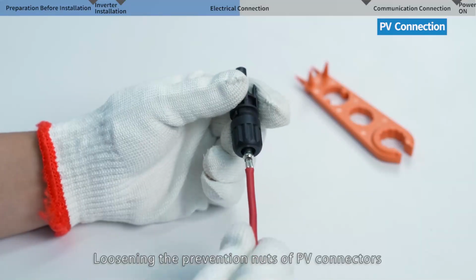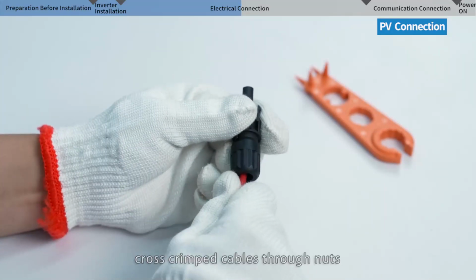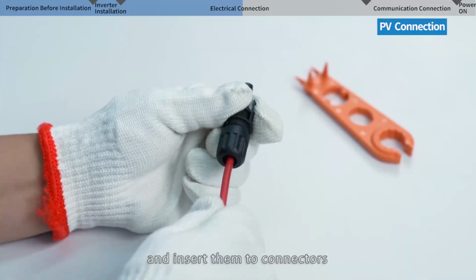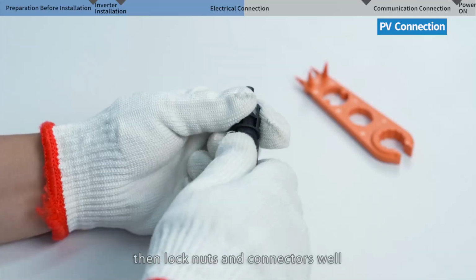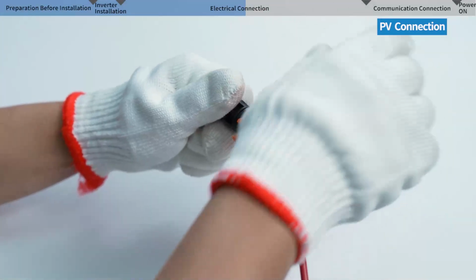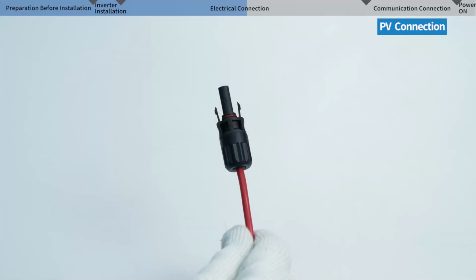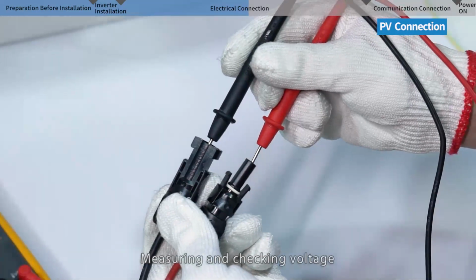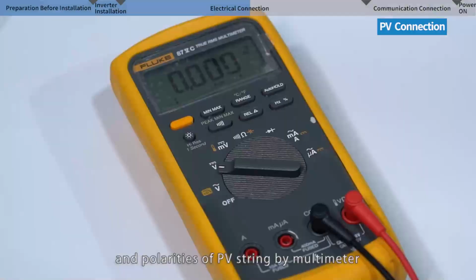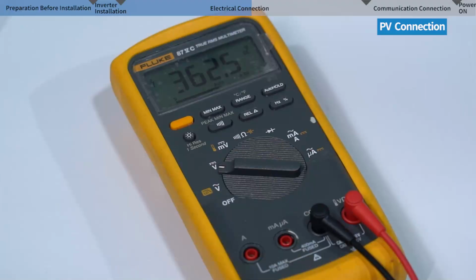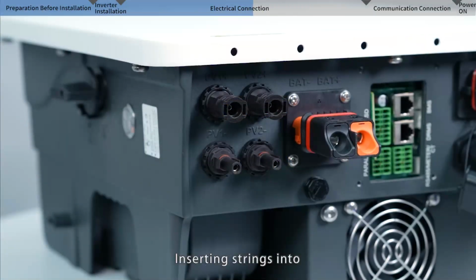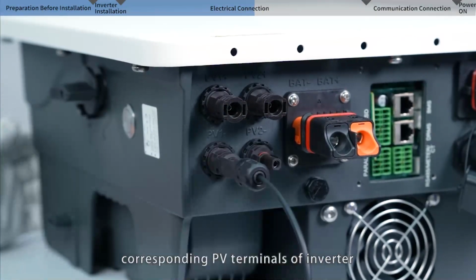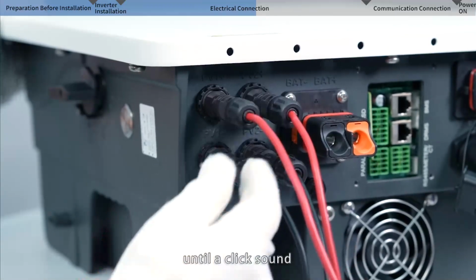Loosening the prevention nuts of PV connectors. Cross-crimped cables through nuts and insert them to connectors. Then lock nuts and connectors well. Measuring and checking voltage and polarities of PV string by multimeter. Inserting strings into corresponding PV terminals of inverter until a click sound.